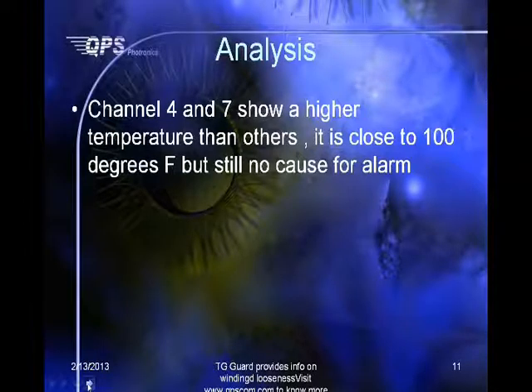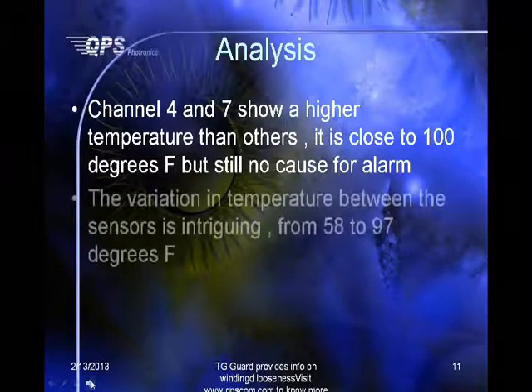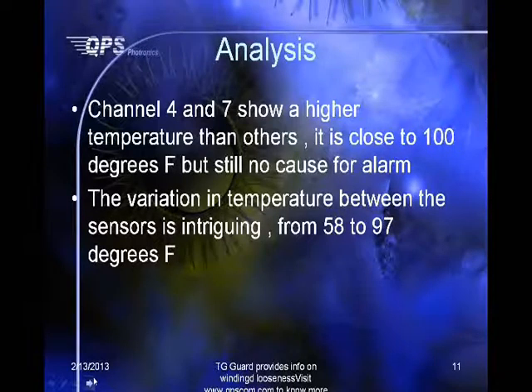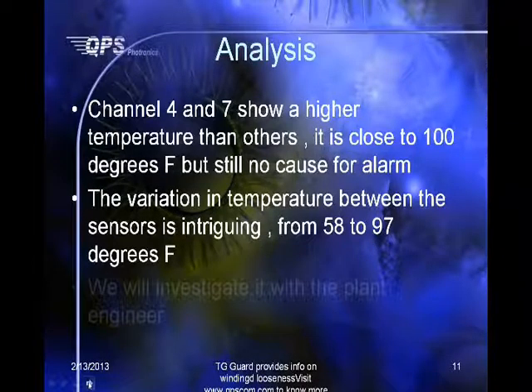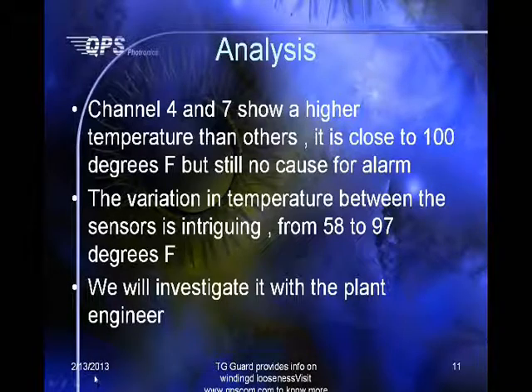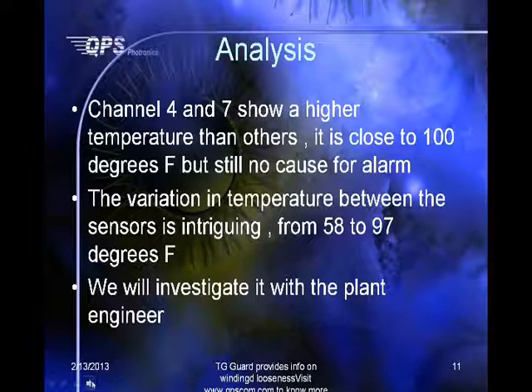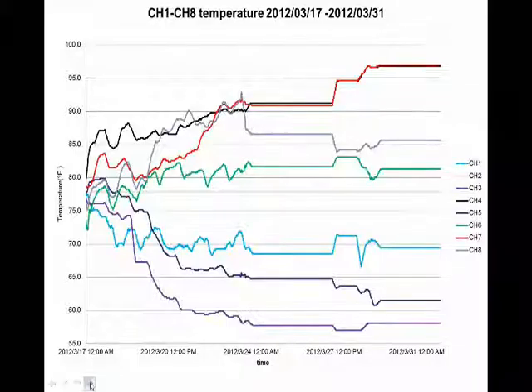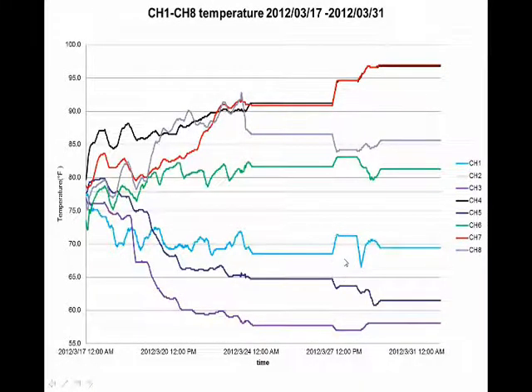So when we do our analysis, we show channels 4 and 7 that are slightly higher. But more importantly, the temperatures are all different, and show a temperature of 97 degrees Fahrenheit, but that's okay. It does compare quite differently with other sensors, whose reading is about half of that. So we're interested in investigating that with the plant engineer. It turns out that the SCADA system can read the water outlet temperature, and so we want to compare the two. Here are the details.